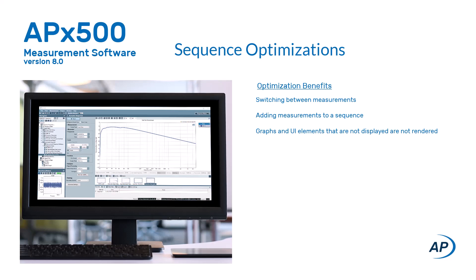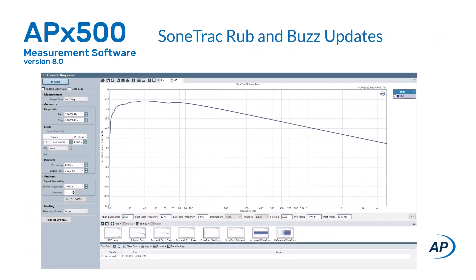Additionally, report data, other graphs, and UI elements that are not visible are not rendered, thereby reducing measurement time. By reducing the number of UI elements displayed — like minimizing the film strip and removing unused measurement results — and excluding non-essential elements from measurements, like unchecking signal path setup in a sequence, measurement times can be significantly reduced.